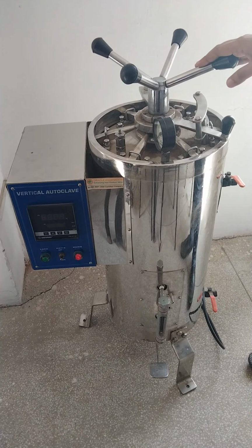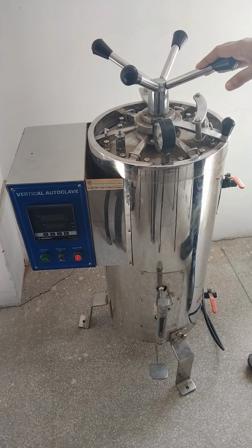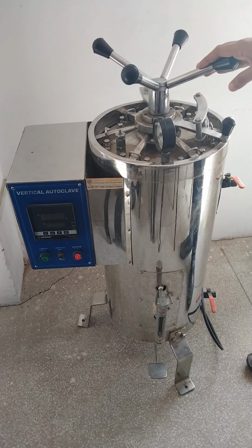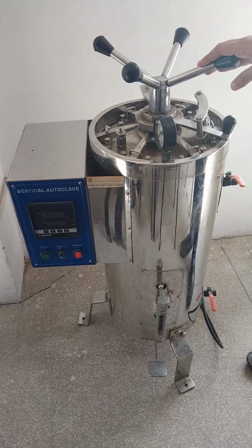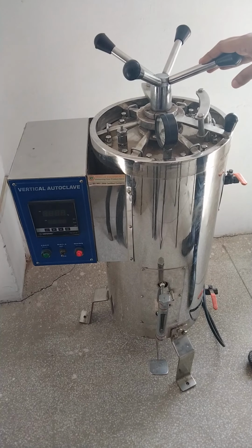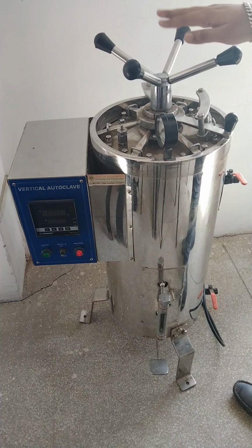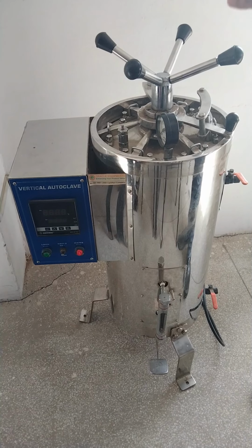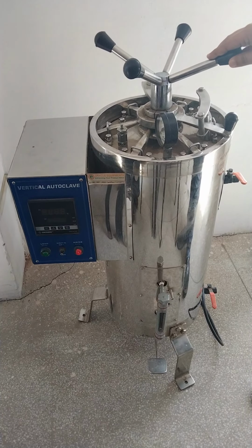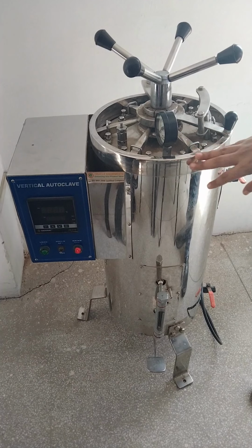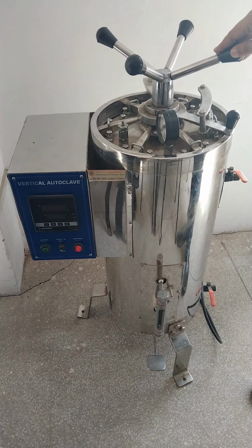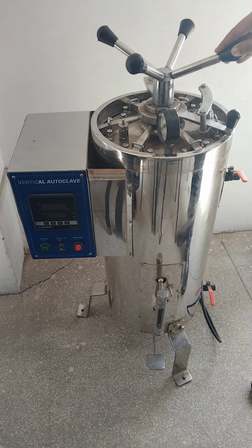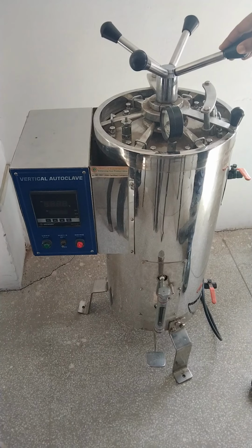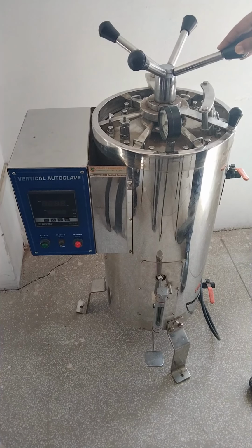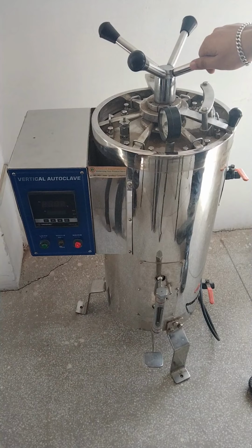One is the pressure cooker type or the vertical type, and the second is the gravity displacement, or you can say the horizontal type. What you are seeing here is a pressure cooker type or vertical type autoclave. These autoclaves are thick-walled stainless steel or aluminum containers designed basically to use steam under pressure. This autoclave has a lid with clamps which fits on the rubber ring over the main container.